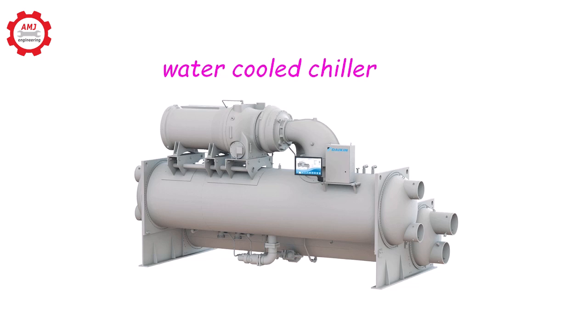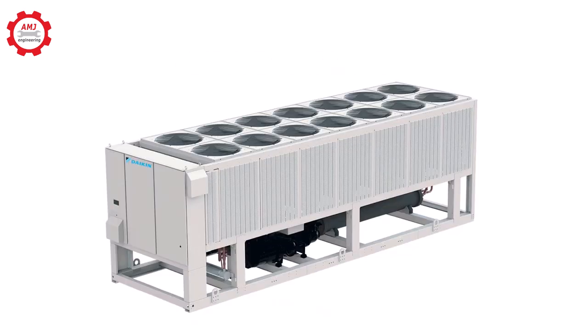Centrifugal compressors: The majority of centrifugal chillers are water-cooled and are often used for medium to large cooling loads from 200 to 6000 tons of refrigeration. You will rarely find a centrifugal compressor in air-cooled chillers.